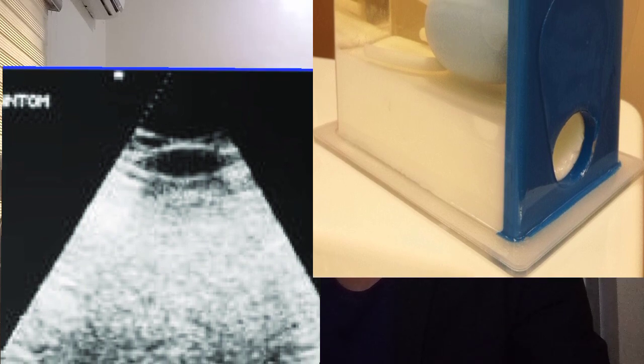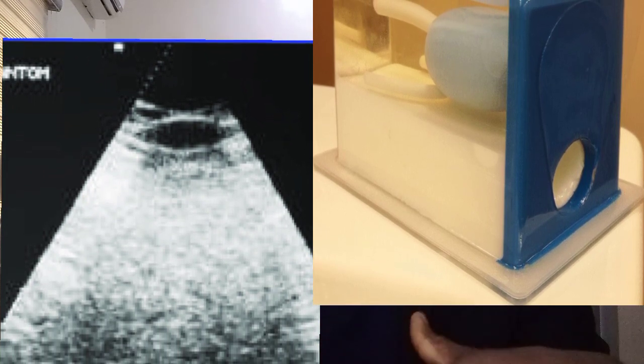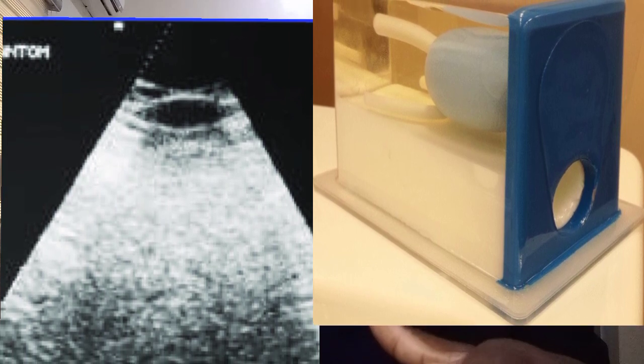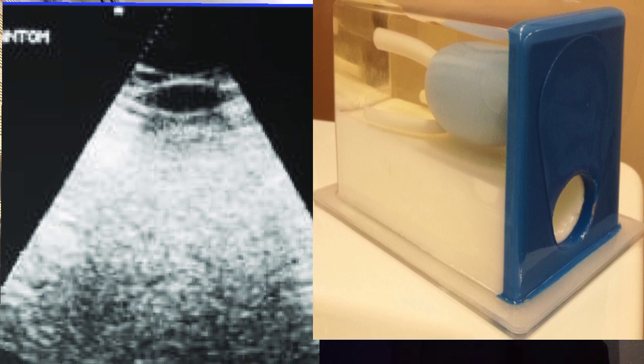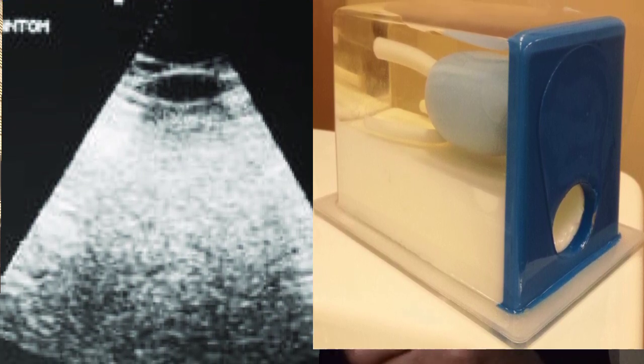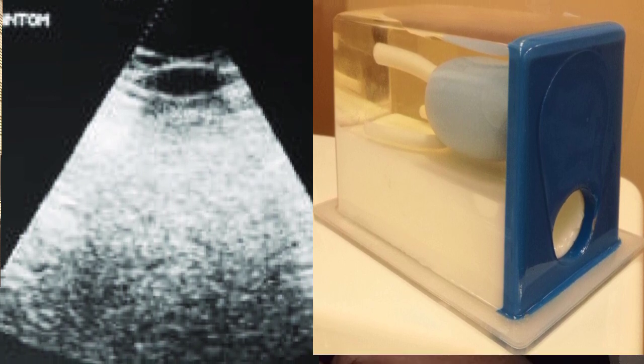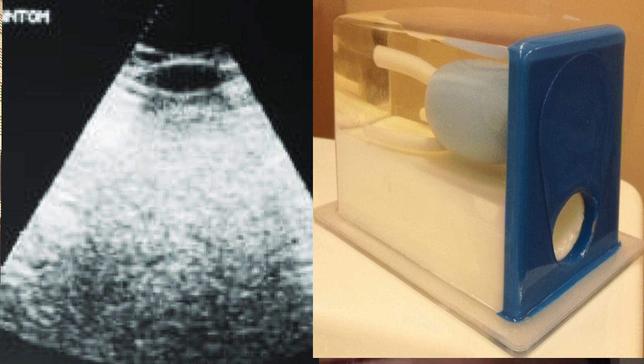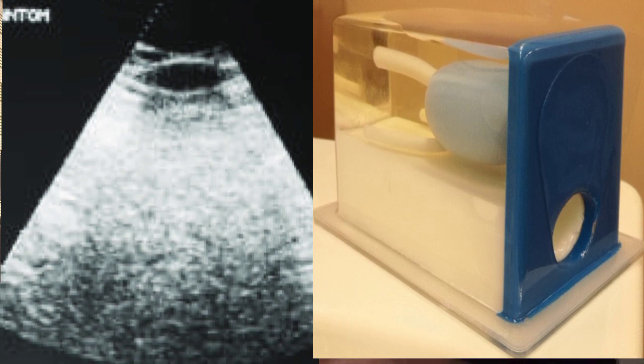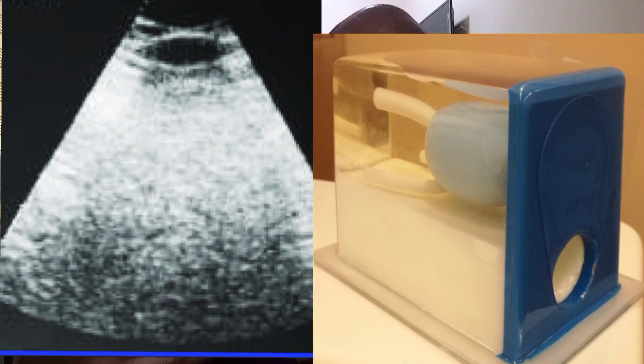Now, a tissue equivalent phantom is a plastic box containing material that simulates the acoustic property of soft tissue. Now, this usually consists of a mixture of gelatin and graphite powder. Within this tissue equivalent material, a pattern of wires and or cysts and solid targets are used to generate echoes. Now, many different patterns are available. A TE phantom attempts to mimic the interaction of ultrasound in the human body to mimic soft tissue and thus better represent a clinical situation. It has several of the characteristics of soft tissue such as propagation speed, scattering coefficient, attenuation coefficient.